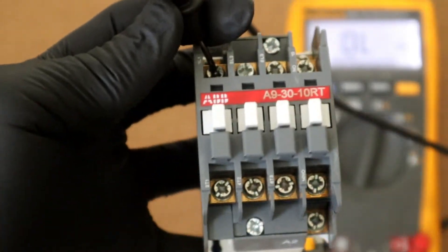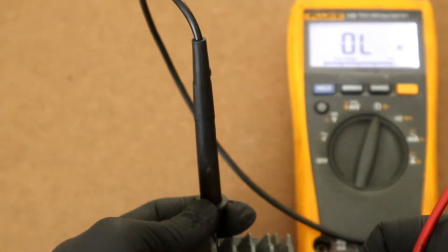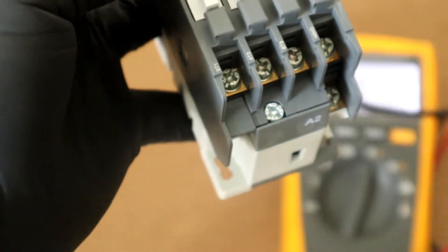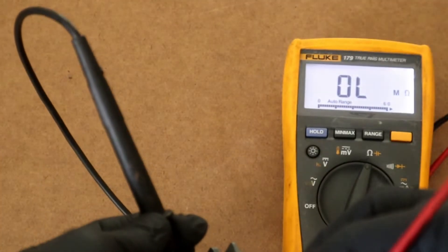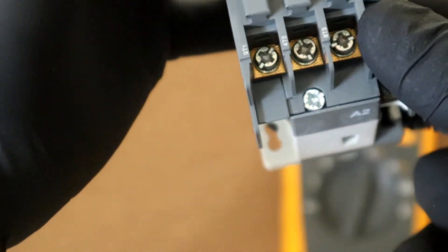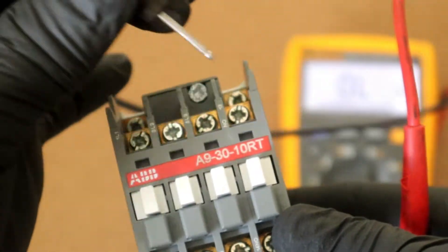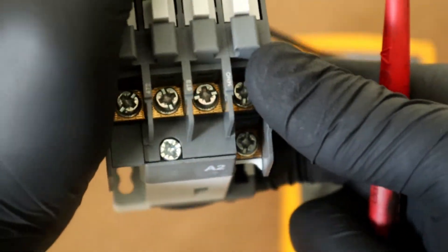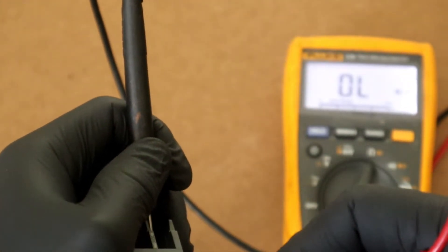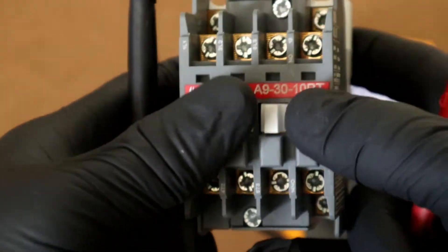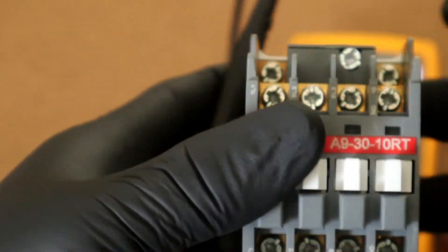So we go across L1, T1, got an OL on our multimeter. We go across L2 and T2, OL on our Fluke. We go across L3 and T3 contacts, OL on our multimeter. We have our normally open contact on the far right. We go across those contact points, OL on our multimeter. The high current, high voltage contact points so far have been good.